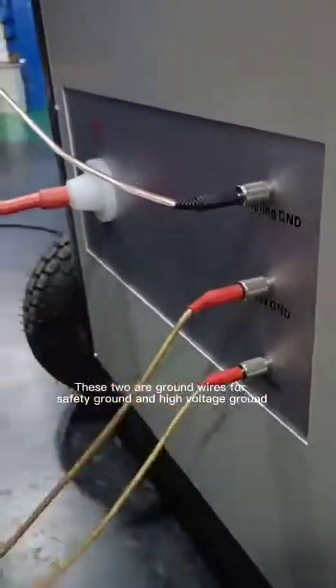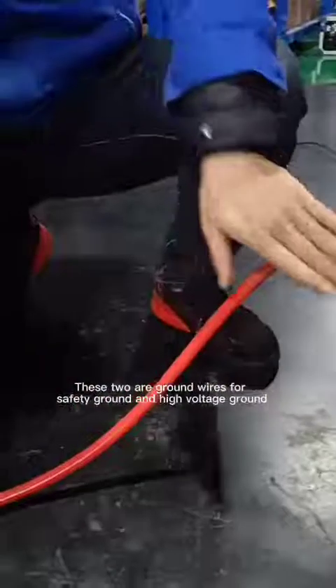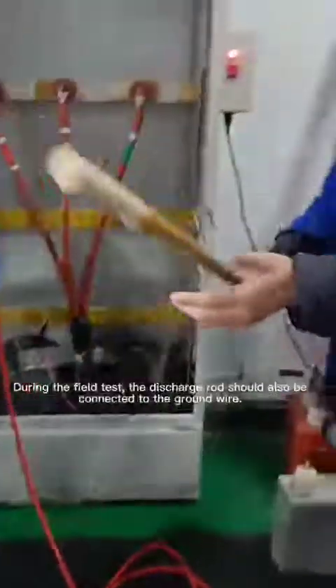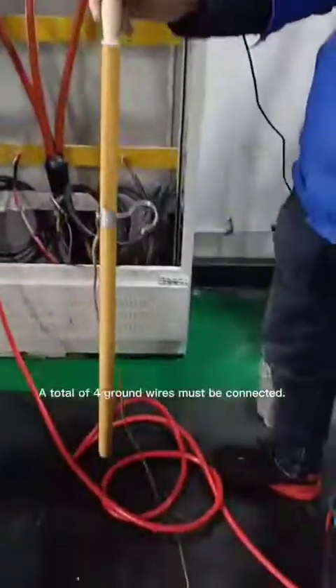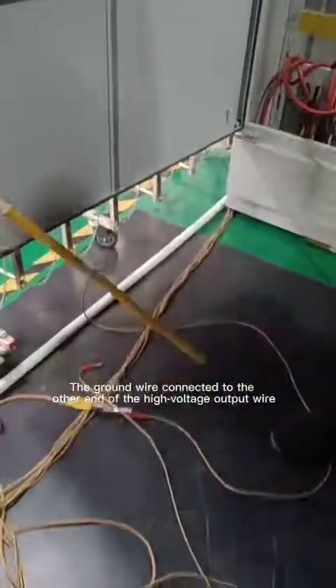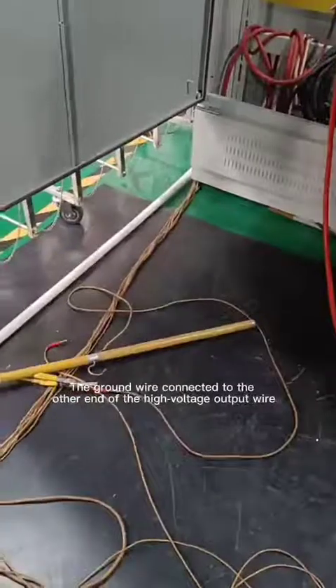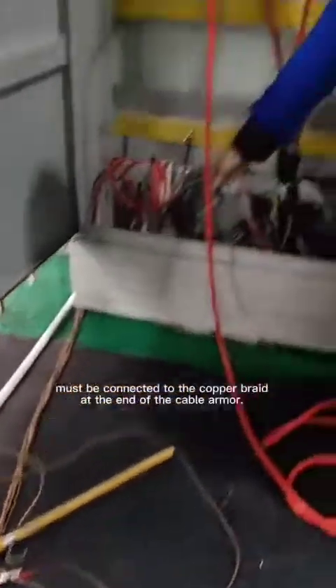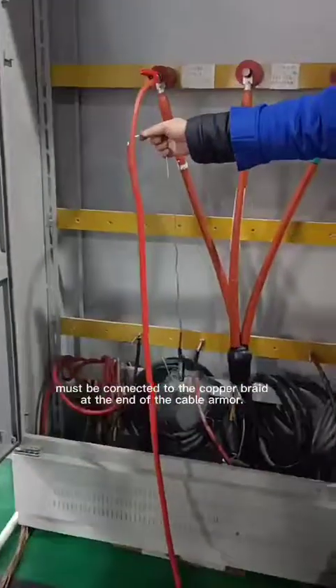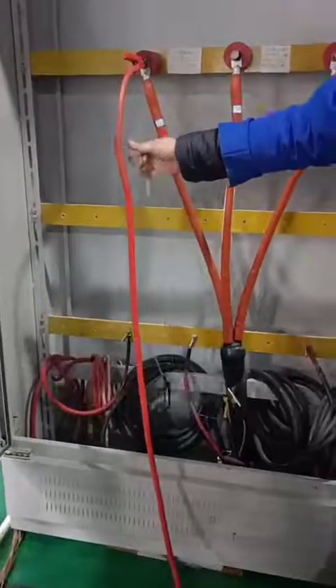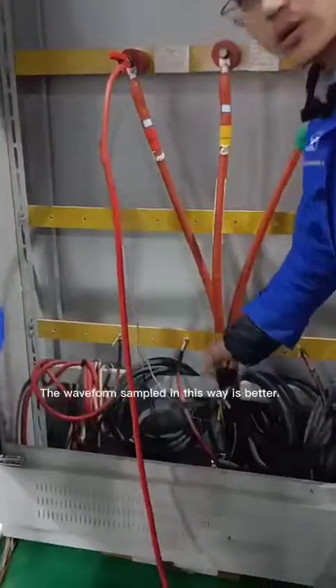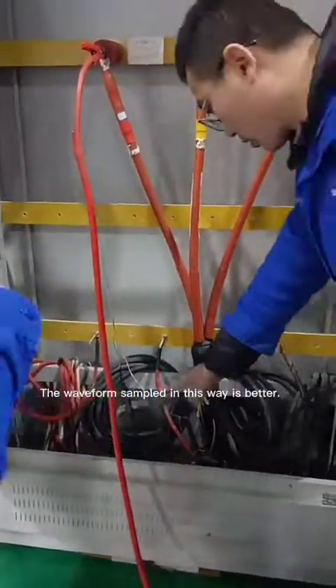These two are ground wires for safety ground and high voltage ground. During the field test, the discharge rod should also be connected to the ground wire. A total of 4 ground wires must be connected. The ground wire connected to the other end of the high voltage output wire must be connected to the copper braid at the end of the cable armor. The waveform sampled in this way is better.